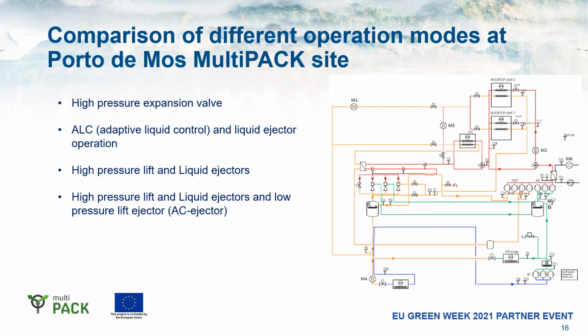So the big question is actually how much does the ejector, or how much do the ejectors together, contribute to the energy saving? In order to indicate the effect of the ejectors implemented in Portugal, we were running several weeks of different operation modes. The first weeks were without any ejector in operation, only the high pressure expansion valve in operation. The second set of measurements were conducted with the adaptive liquid control in operation, so minimize superheat on the evaporators, and the liquid ejector, so to say, moving the liquid from the suction gas accumulator or suction gas separator back to the receiver pressure level and the receiver.